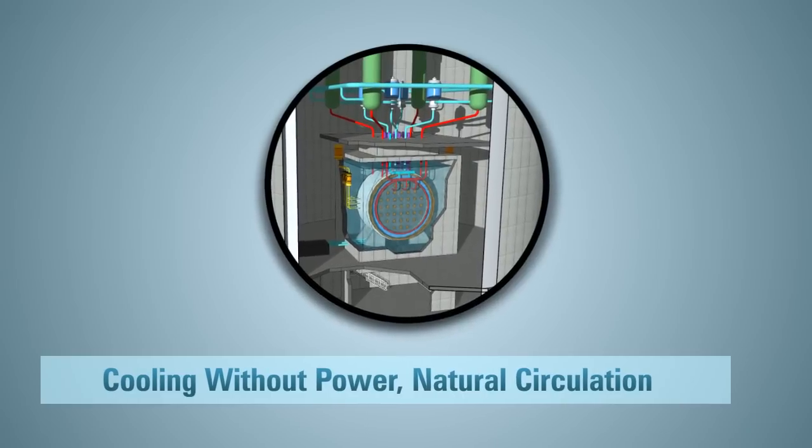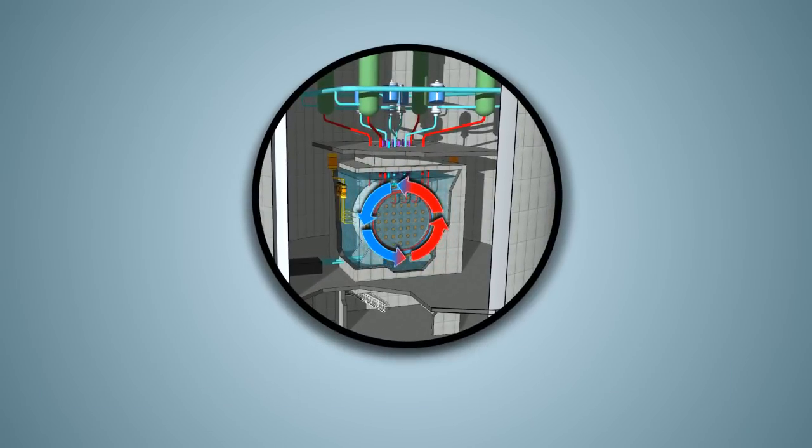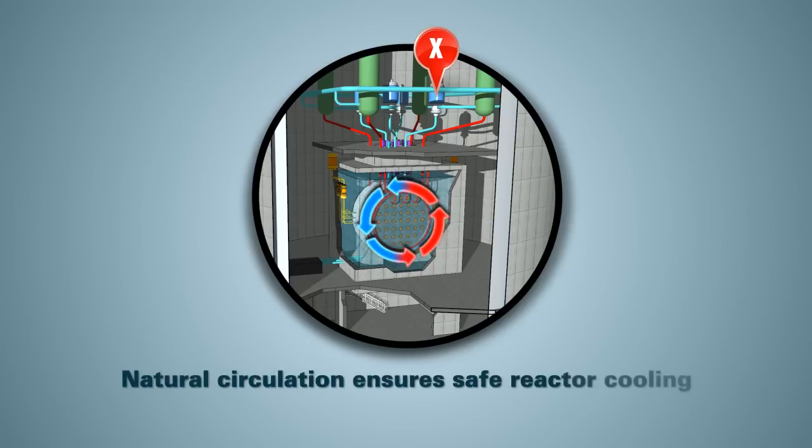To reduce this heat, natural circulation takes over when the pumps that normally push the coolant through the heat transport system lose power and stop working. For natural circulation to continue over time, the steam generators need to be filled with cool water.